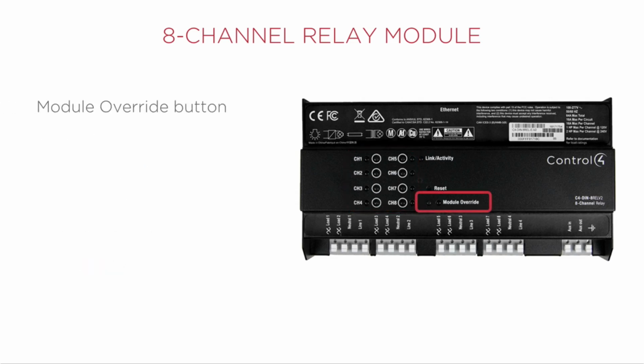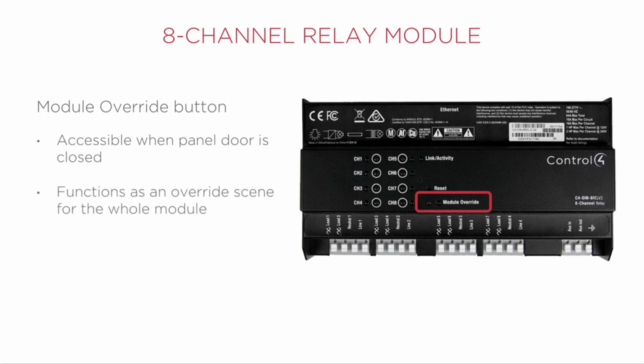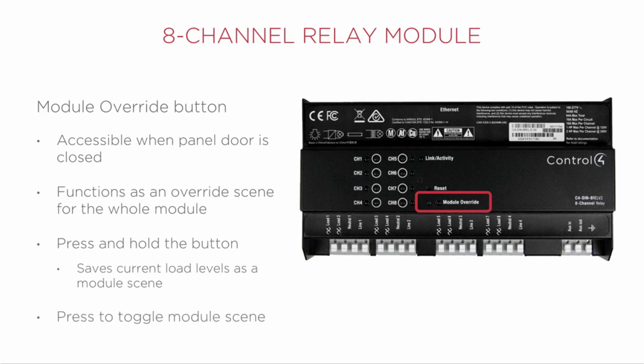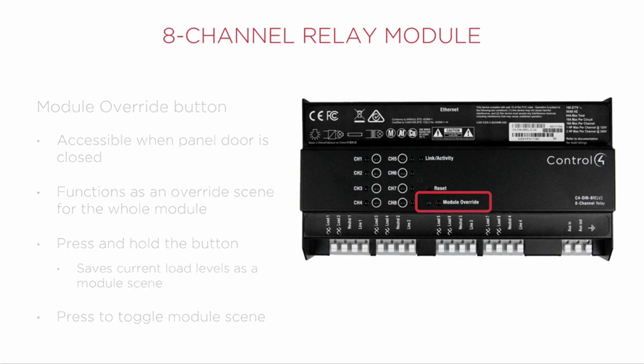There is a module override button accessible when the panel door is closed, which functions as an override scene for the whole module. After the loads have been set to their desired state, press and hold the module override button to save a module scene. Pressing the module override button will toggle that module scene.